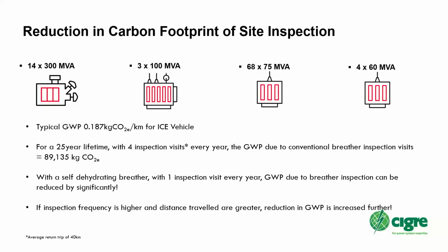With a self-dehydrating breather, I'll probably only need to go once, and that trip can be tagged for other purposes as well. So we're able to reduce the additional carbon footprint just for traveling. If inspection frequency is higher and distances traveled are greater, here I'm assuming only 20 kilometers up and 20 kilometers down, but if you travel more, your GWP goes up, adding to the life cycle assessment of your transformer.